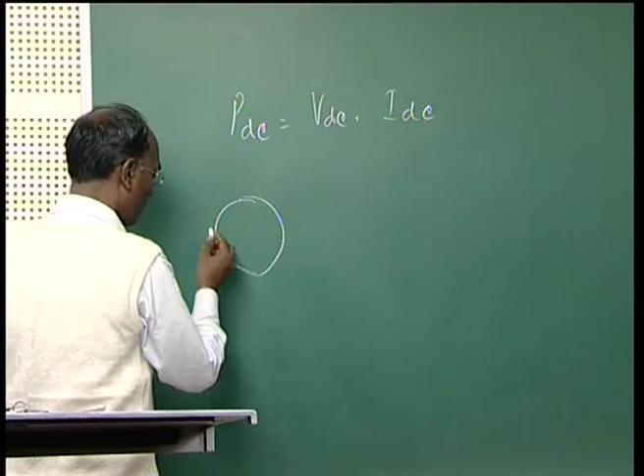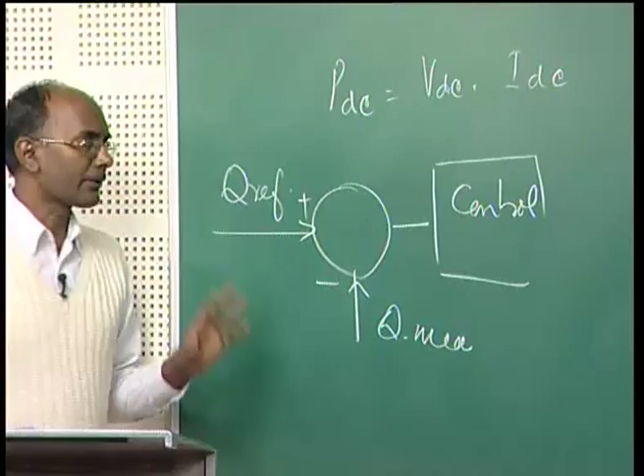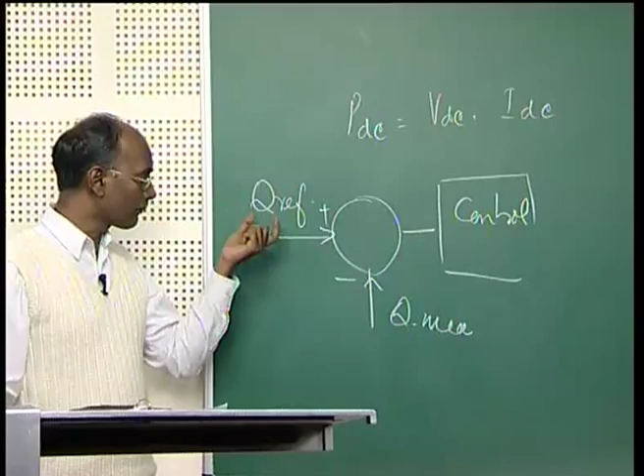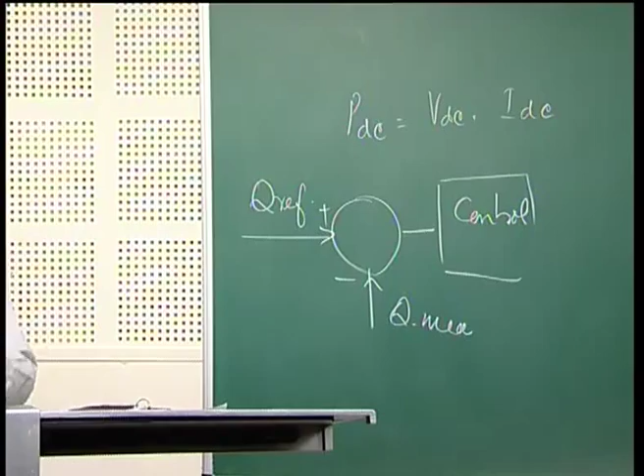Here I am talking about controlling the reactive power. The reactive power controller is normally a PI controller, the proportional integral controller. The measured Q reactive power and the desired reactive power are the inputs to the controller. Here is the control block: Q ref is the reference reactive power you need, and this is your measured value, with a plus and minus. The intention is that this error should be minimized by the controller, so that the measured Q equals the Q reference, and the difference goes to the controller.